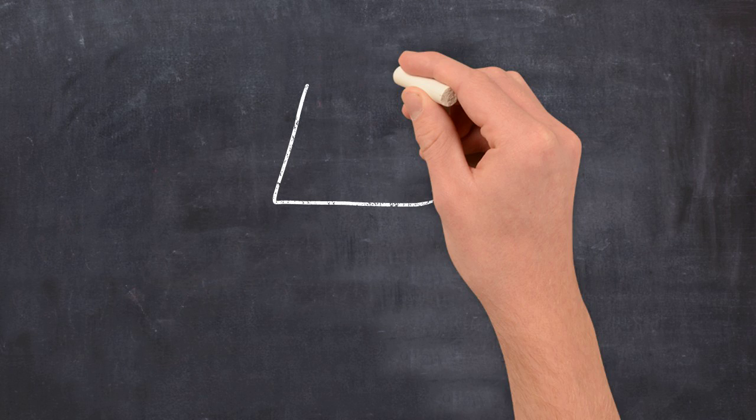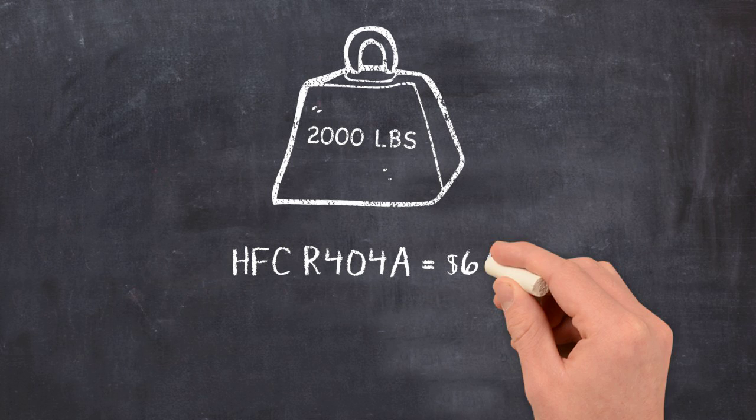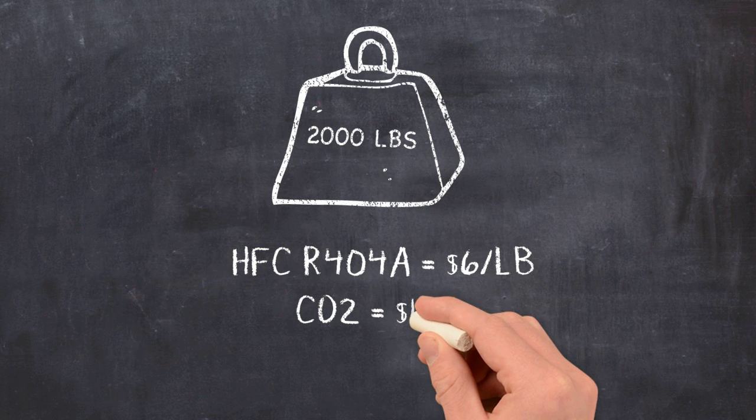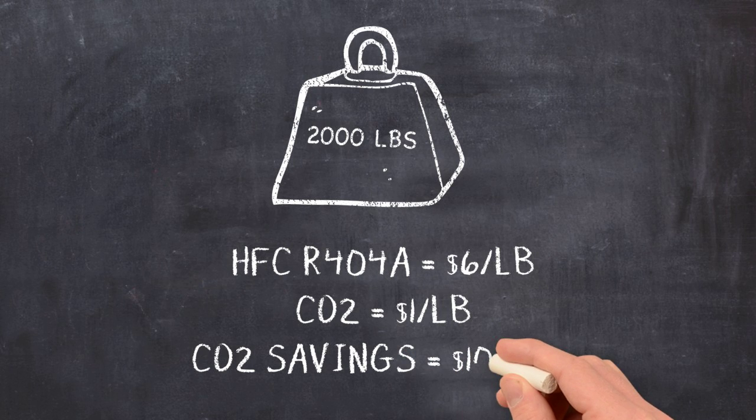Let's say a store needs a startup charge of 2,000 pounds of refrigerant. HFC-based refrigerant costs around $6 per pound, but CO2 refrigerant comes in at just $1 per pound.